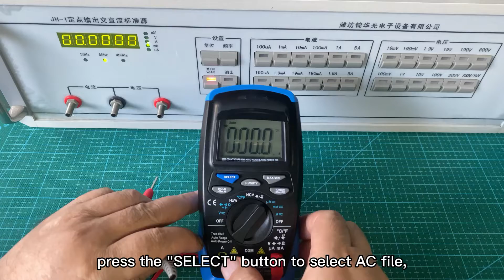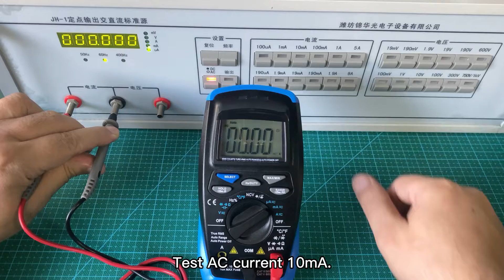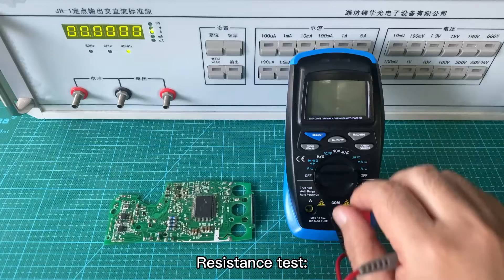Test AC current. Press the select button to select AC file. Test AC current 100 uA. Test AC current 10 mA. Please note that the instrument defaults to the DC gear in the current gear, and you need to reselect it when changing the range. Resistance test.